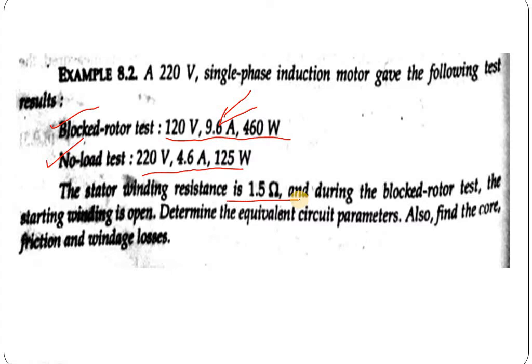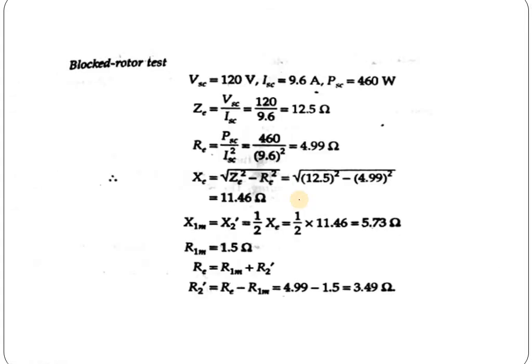The problem will be solved in the same way as we calculated the equivalent circuit parameters per our previous lecture. We will start our calculation with the block rotor test. In the block rotor test, the values given are: voltage at short circuit VSC equals 120V, meaning at block rotor test the applied voltage is 120V. ISC equals 9.6A, that means the short circuit current is 9.6A. And PSC equals 460W, which is the power input at block rotor test condition.